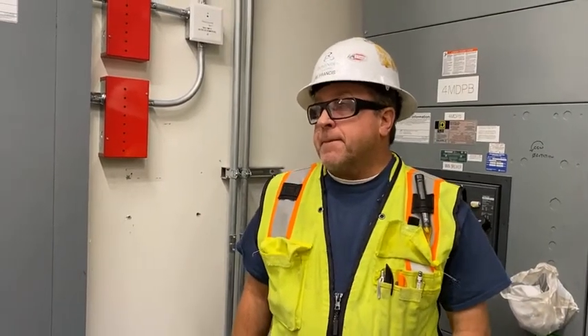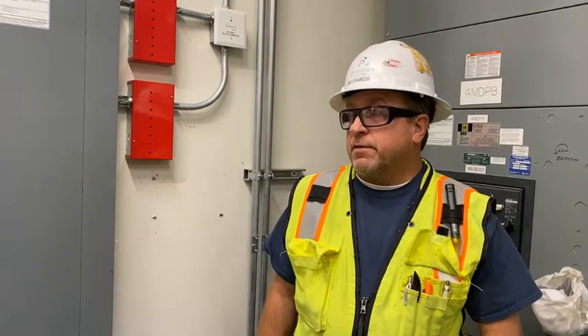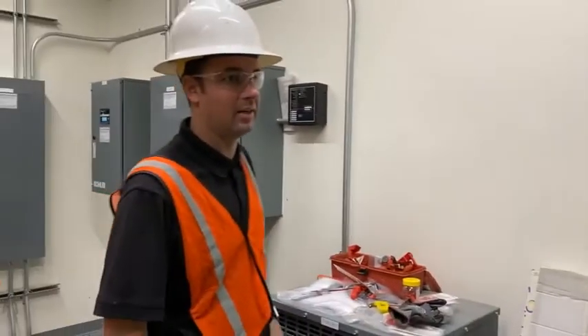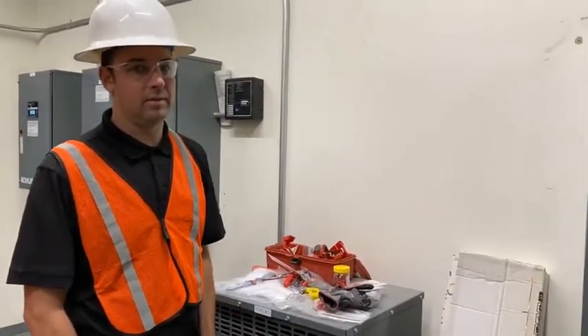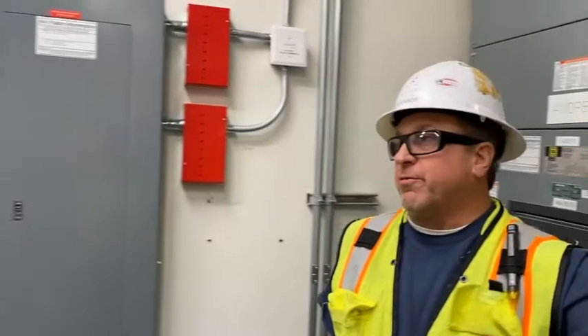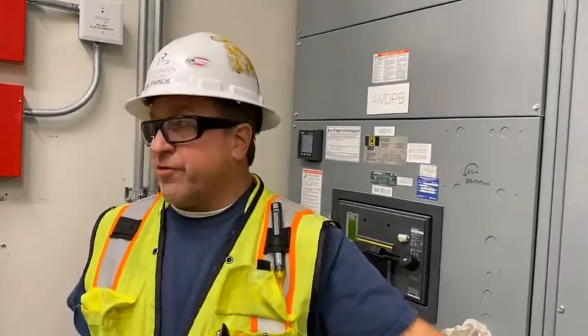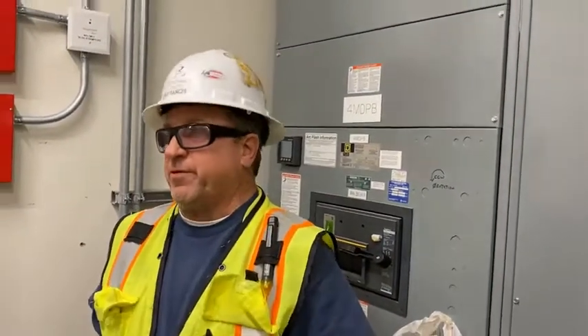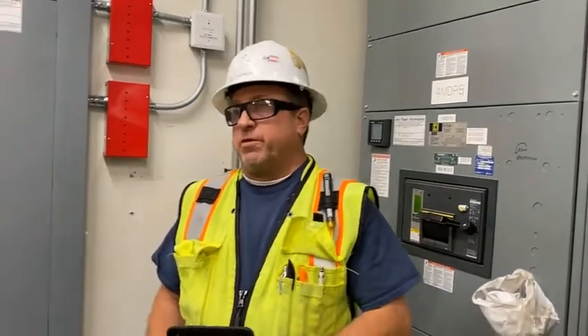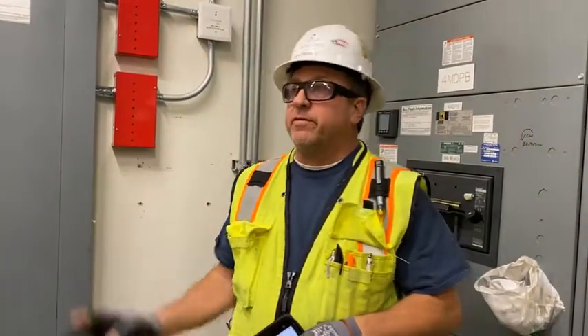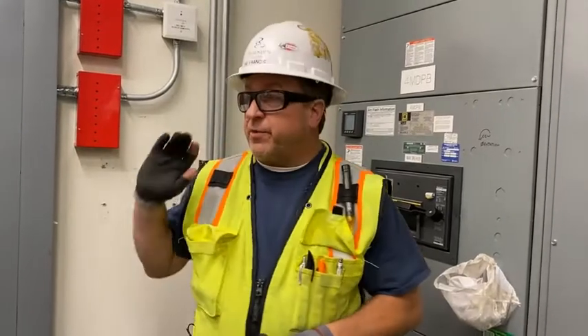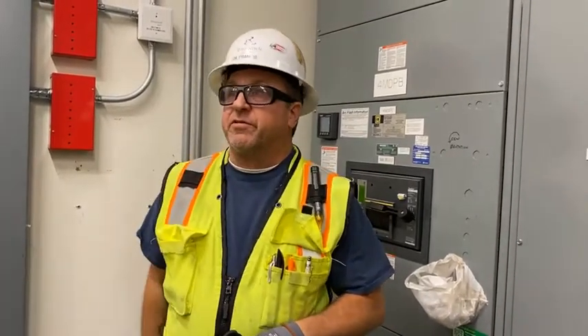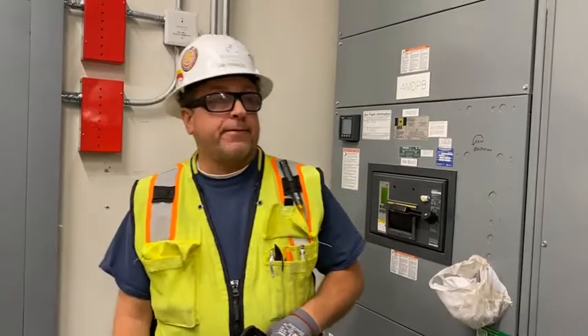It starts right up. So if we need to shut down that panel that's tied to the ATS, we would have to shut down the ATS, correct? Well, we would have to lock out the generator and lock out the feed for this. Even though the generator's not running normally, if you just turn this off, it would kick on. Turn it off right now and it generates. It would, yeah, because it's got 2 start wires that go out to there. If I were to turn this off, you would hear a click in there, which is sending the signal out.